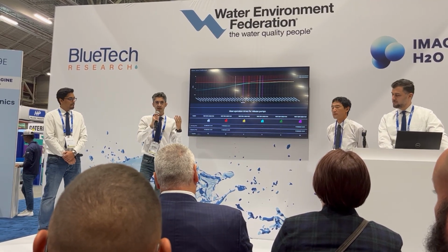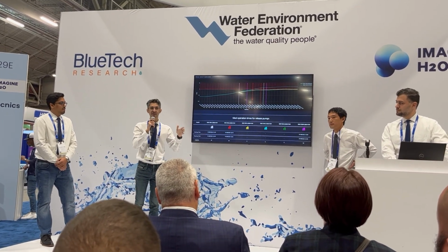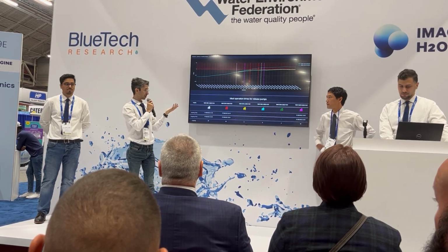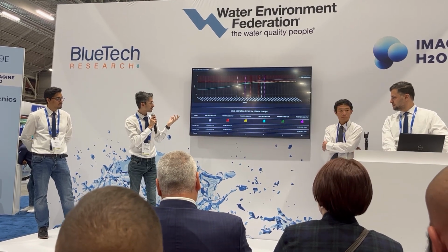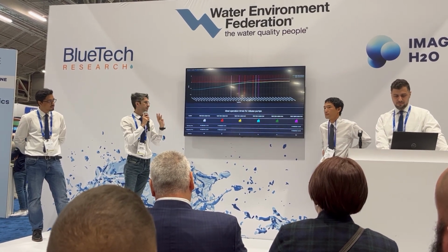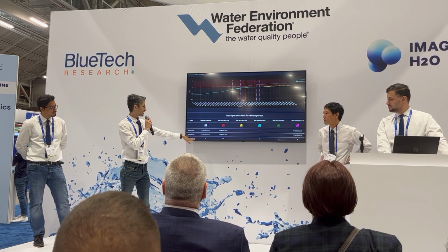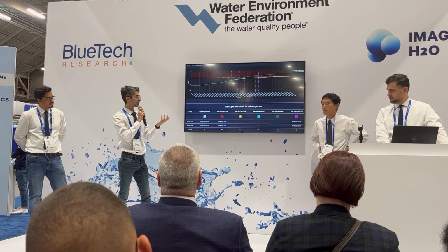Wet weather treatment process, given that it uses a lot of chemicals, is much faster but also costly. So our goal here is to minimize the amount of wastewater sent to the wet weather treatment process rather than the complete treatment process, while minimizing the risk of overflows. And to do that, we developed 3 components. If we look at the table, we can see what are the proposed times and capacities for each pump to operate.